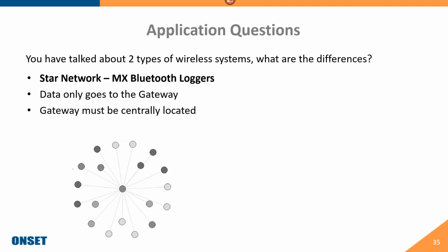At the onset building, for example, I ended up having to use 2 gateways just because we happen to have our server farm right in the middle of the building, and that actually blocks a lot of the Bluetooth traffic getting back to one particular gateway.